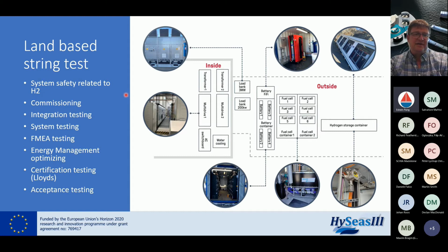The string test itself has enabled us to learn a lot about system safety related to hydrogen and the commissioning, both related to hydrogen and integration of the hydrogen between the storage and the fuel cells, but also new functionality related to DC switchboards that we have developed during this project. We had a lot of system testing together with FMEA testing to be sure that we have a safe system.